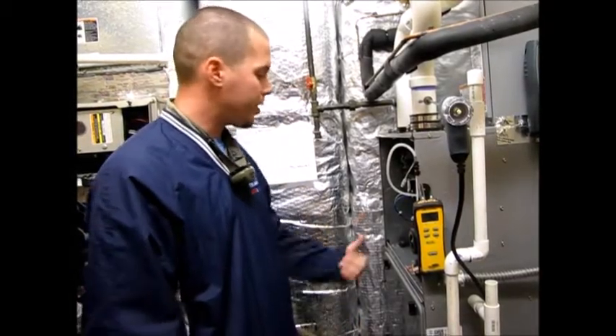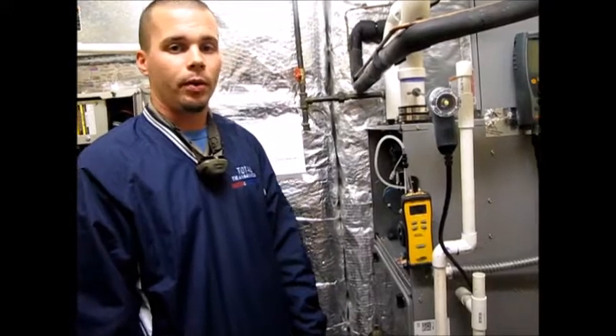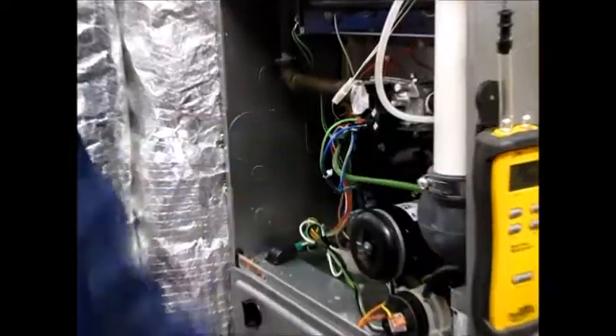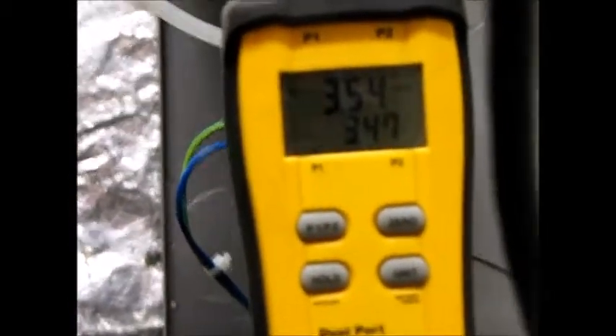Another key factor to a furnace check is to make sure that you've got proper pressure running through the gas manifold. This manifold is rated for about three and a half inches of water column. By my manometer we're showing that we're just slightly above what we're calling for. And one deduction that we did on our previous combustion analysis, we're getting kind of a high stack temperature.